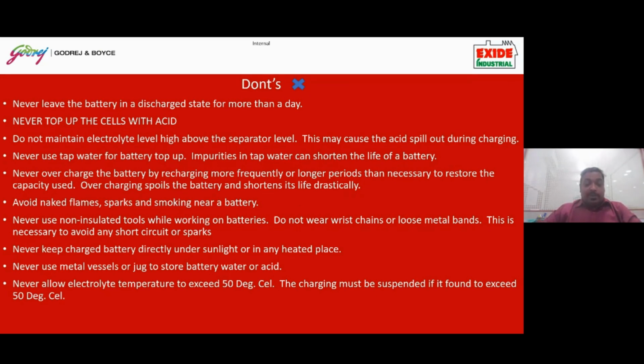So never use non-insulated tools while working with the batteries. And as I already told you, wrist chains, loose metal bands, rings, all these things must be removed when you're doing battery maintenance. Now, metal vessels and jugs should not be used to store battery water or acid. It should always be either stainless steel or preferably high grade plastic. The temperature of the cell is also very important. It should not be allowed to go beyond 50 degrees. So these are the main do's and don'ts.